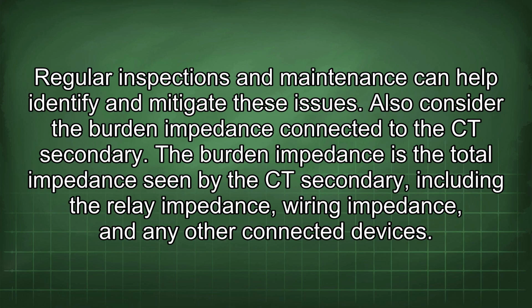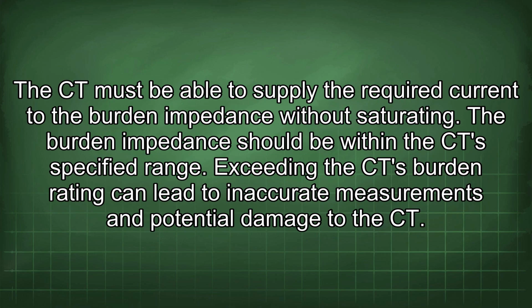Also consider the burden impedance connected to the CT secondary. The burden impedance is the total impedance seen by the CT secondary, including the relay impedance, wiring impedance, and any other connected devices. The CT must be able to supply the required current to the burden impedance without saturating. The burden impedance should be within the CT specified range. Exceeding the CT burden rating can lead to inaccurate measurements and potential damage to the CT.